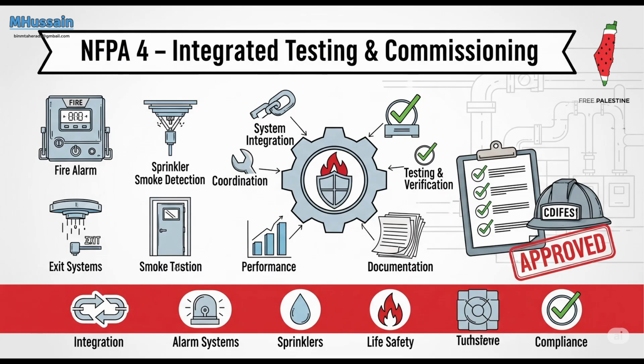Or, and this is really important today, when changes are made to the site-specific software for an individual system that's part of that integrated network. So anytime you significantly change the setup or the programming, you have to re-verify the integration. Anytime you potentially mess with the harmony, you need to run checks to make sure the whole piece still works together correctly. Okay, that covers the who, what, how, and when.